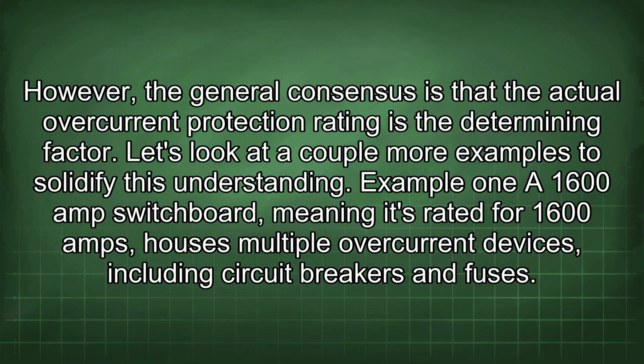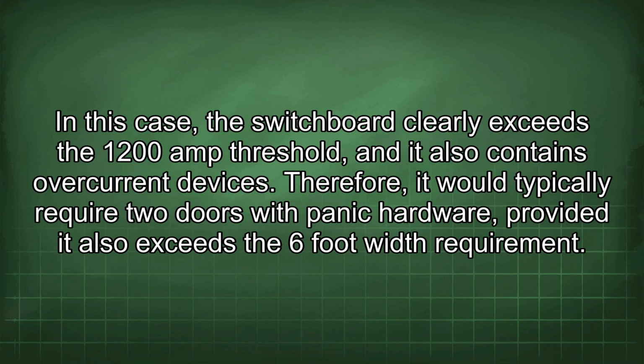Let's look at a couple more examples to solidify this understanding. Example 1: a 1600 amp switchboard, meaning it's rated for 1600 amps, houses multiple overcurrent devices, including circuit breakers and fuses. In this case, the switchboard clearly exceeds the 1200 amp threshold, and it also contains overcurrent devices. Therefore, it would typically require two doors with panic hardware, provided it also exceeds the 6-foot width requirement.